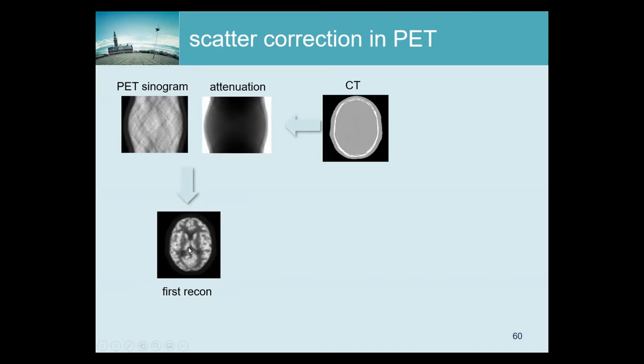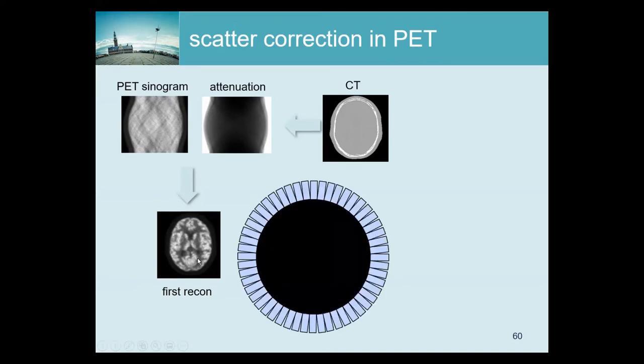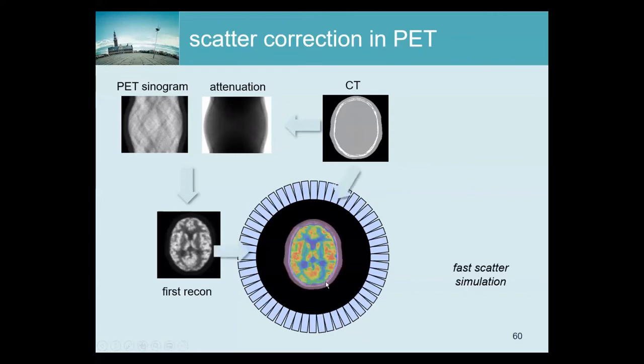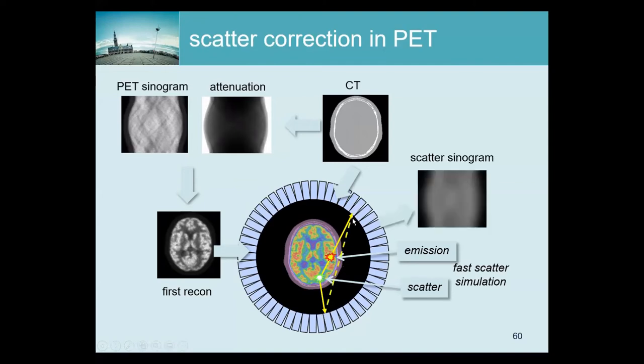We assume it's not too bad, so based on this we can estimate the scatter. We have an estimate of the activity and an estimate of the attenuation image, so we can put that into the simulator, and the simulator will simulate how the scatter is being formed. For example, two photons are emitted: one goes directly into the detector, the other is scattered and goes elsewhere. With Monte Carlo that would take forever but would be very accurate. Methods have been developed to do this much faster with variance reduction techniques, so now we get a scatter sinogram.